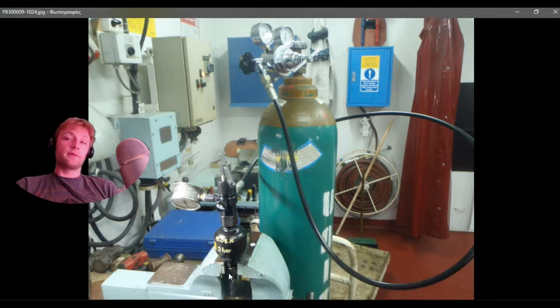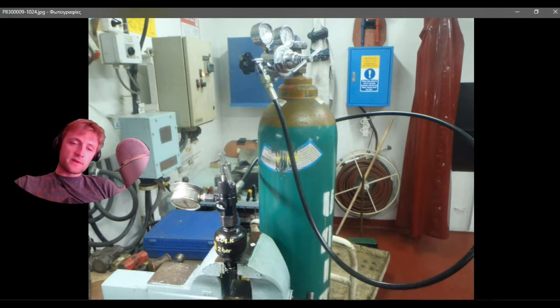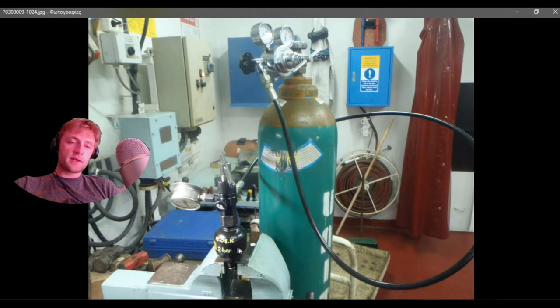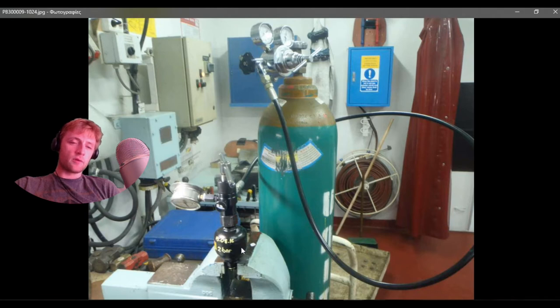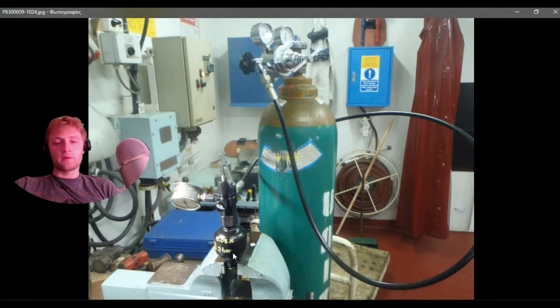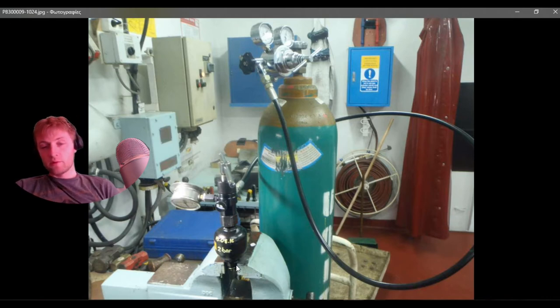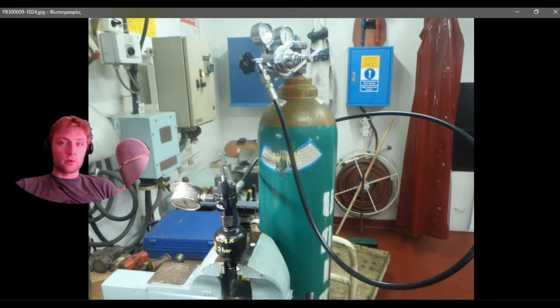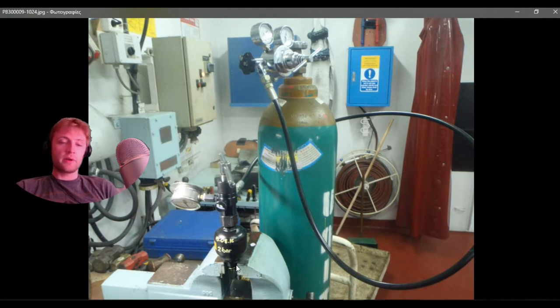Then you will look for nitrogen leakage. If you have nitrogen leakage, that means the membrane which is located inside here is damaged and the nitrogen is passing from this side on the top to the oil side. This membrane separates the nitrogen from the oil, that is the main purpose of this membrane.